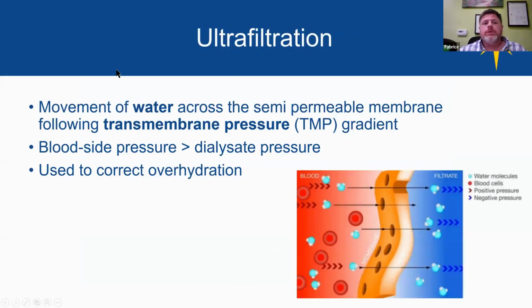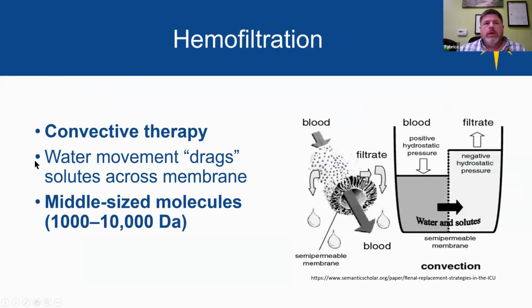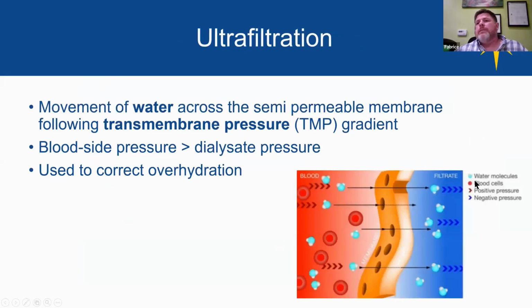Ultrafiltration. Here we're talking about movement of water through the membrane, and that's allowed by the transmembrane pressure. On one side of the membrane, in this case, you have the blood here on the left, and the filtrate here on the right. You will have a higher pressure in the blood and a lower pressure in the filtrate, and on both sides of that membrane in the middle, that will drag the water out. That is important for a patient who is overhydrated, if they are in acute kidney injury, or also a cardio patient that is overhydrated too; you will be able to remove the fluid.